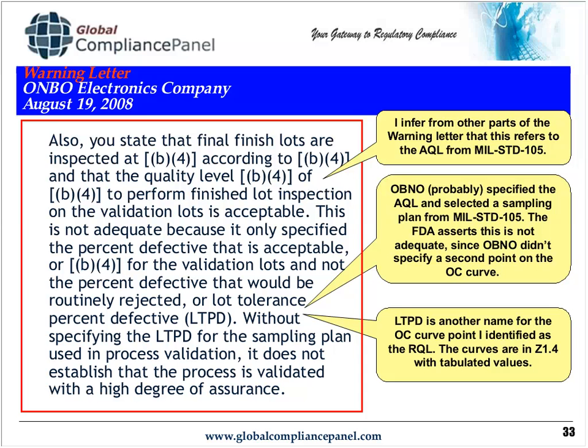Now, what they're saying here is that this company is naming the AQL point, and they're not looking at what's called the lot tolerance percent defective, which on my OC curve I call the RQL point. They mean the same thing. Without specifying the two points on the curve for the sampling plan, it does not establish that the process is validated with a high degree of assurance.